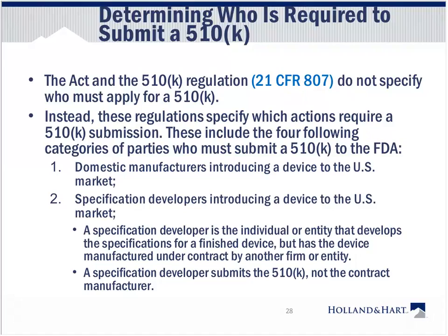I told you we'd get to specification developers. What do we mean by that? A specification developer is an individual or entity that develops the specifications for a finished device but has the device manufactured under contract by another firm or entity. It happens a lot with the new disruptive medical innovations out there. They come up with an idea. It may be an app, it may be a mobile app, it could be any number of things. The ideas are all there, but the product itself is going to be created by a contract manufacturer. In that case, the specification developer is responsible for the 510K. As I say there, the specification developer must submit the 510K, not the contract manufacturer.